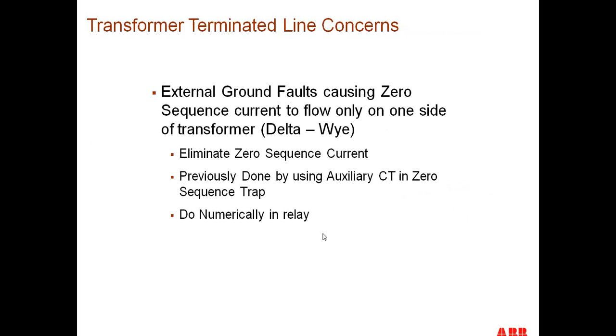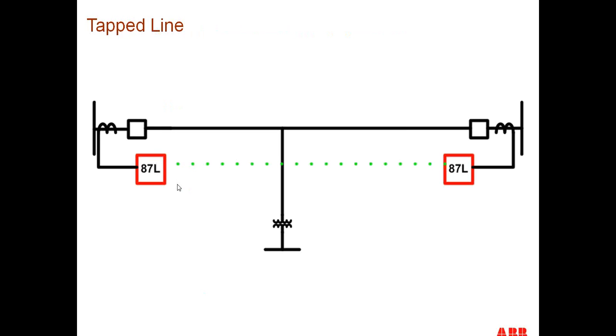So we use zero sequence elimination, and we used to do this with a zero sequence trap with an auxiliary CT, but now we can do that same thing in the relay. Another example would be a tapped line, where we have a tap line with a transformer connection at the tap. We used to handle this by setting the pickup level of the 87L element above the value of the load current on this tap. We don't need to do that anymore, and we can handle this another way.